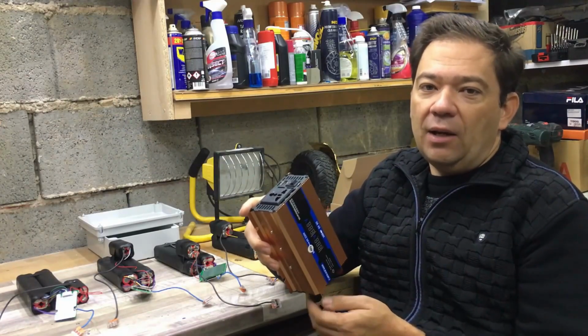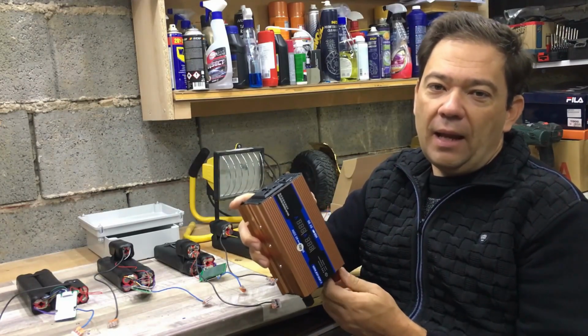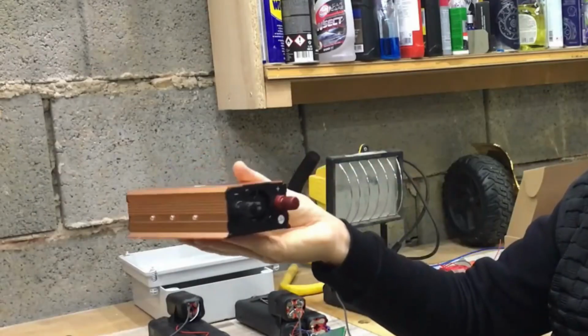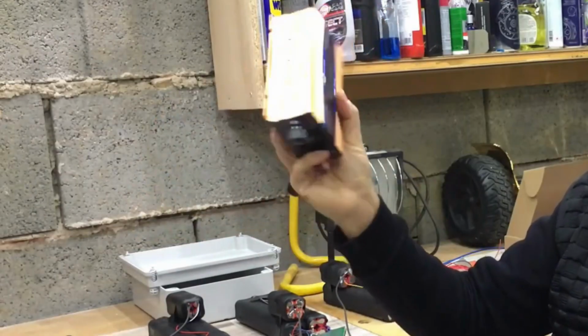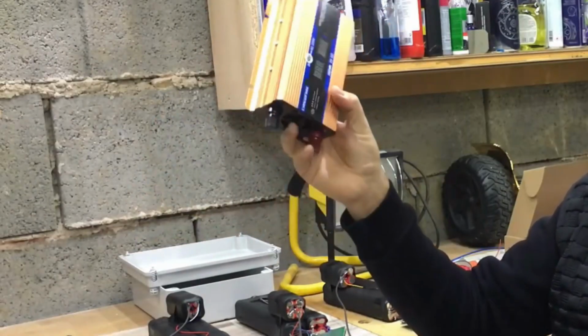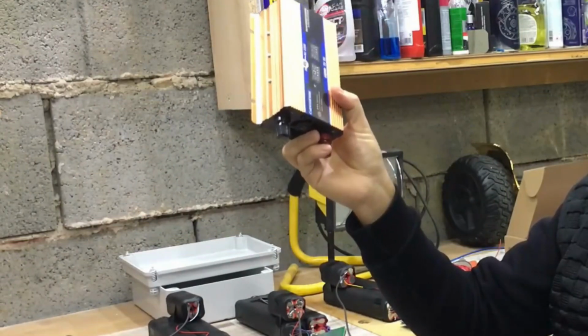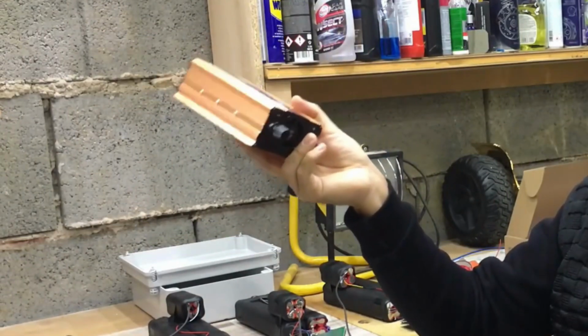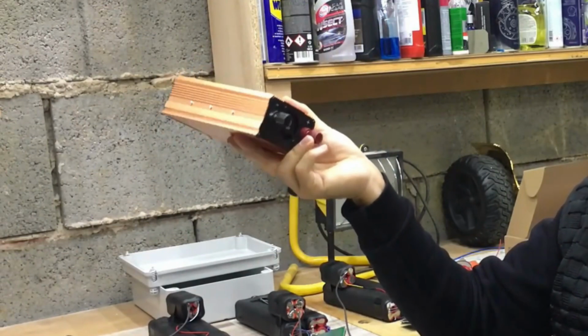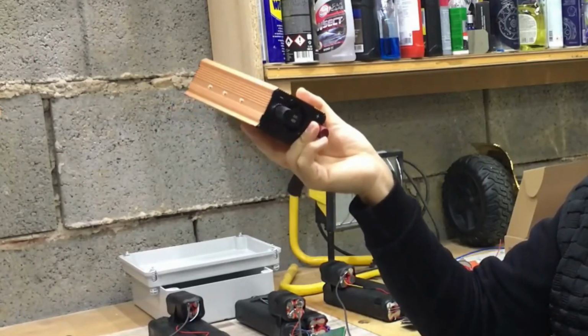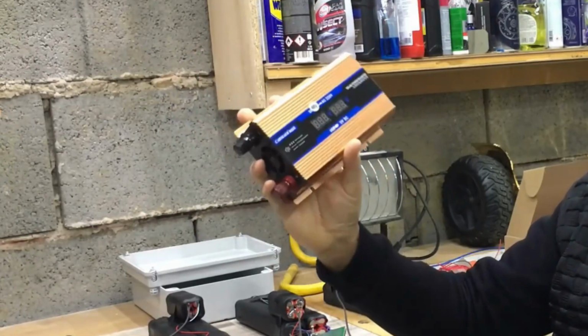It can handle 800 watts continuously, but that 800 watts is actually about 500 watts. So with this type of inverter, one about this size, you shouldn't be fooled into thinking you can actually deliver 2 kilowatts. If you connect 2 kilowatts to it, one of two things will happen: either it will break, or it will simply shut off due to overload.